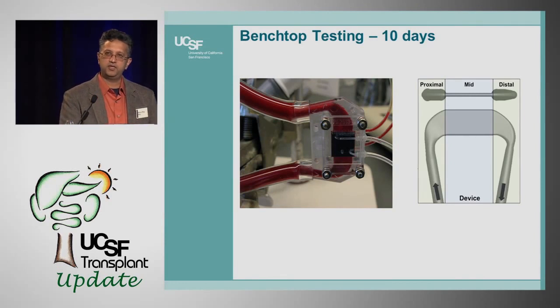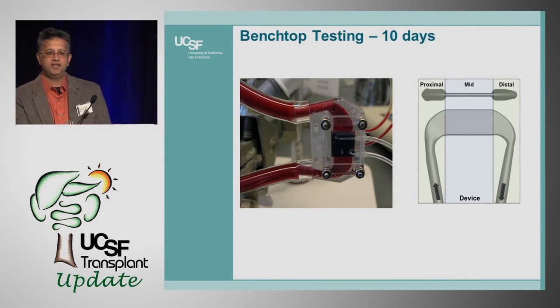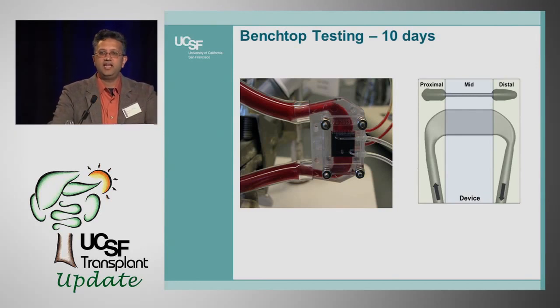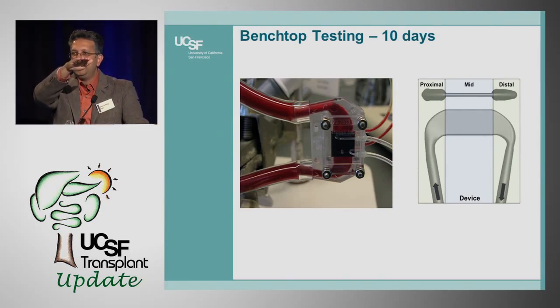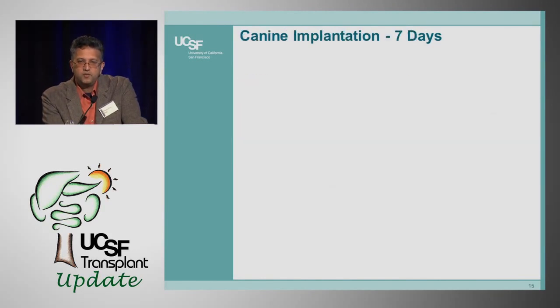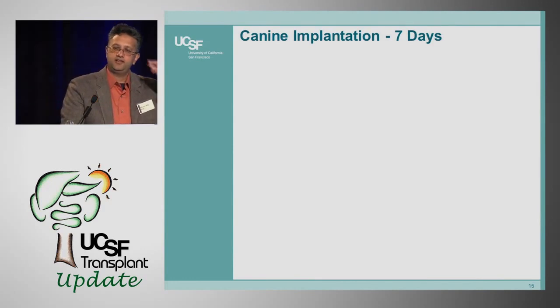So what we did was we looked at the flux through the membrane on day one, and then looked at the flux on the membrane every day. And we put it in, it just dropped by 3% and stayed constant throughout the rest of the test. What that told us was our coating was stable, was not moving off the membrane, but secondly, it was doing its job of trying to retard protein fouling. So with that progress, we said, well, let's continue to advance the filter technology.